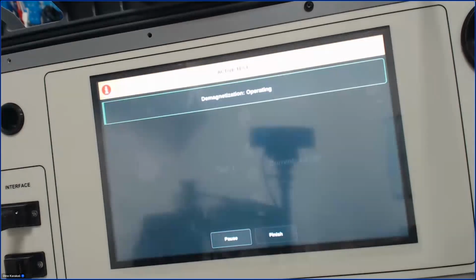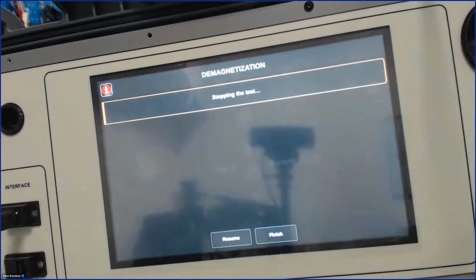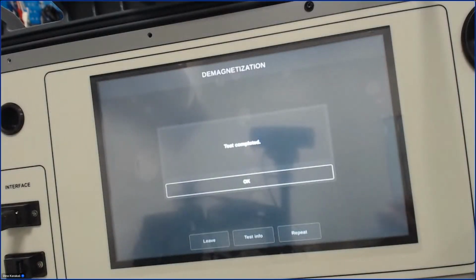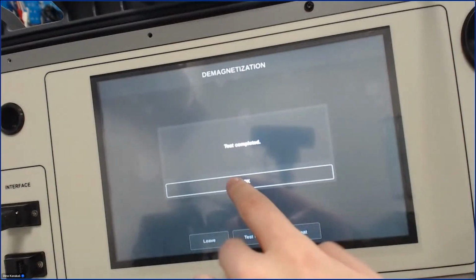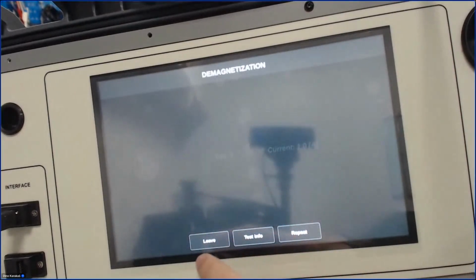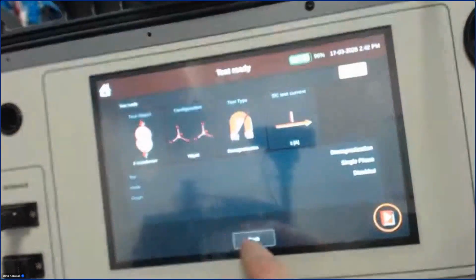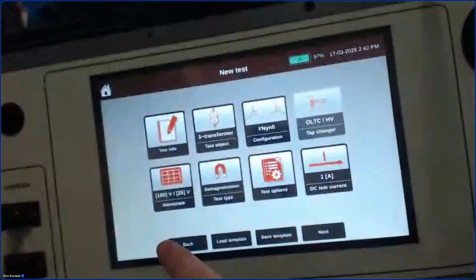If you can hear relays working, it means the test is on, and of course the device shows that the test is active here. So we wait a little bit until the core is demagnetized, and the demagnetization is completed right now. We press OK. And the last test for today will be the turn ratio test.